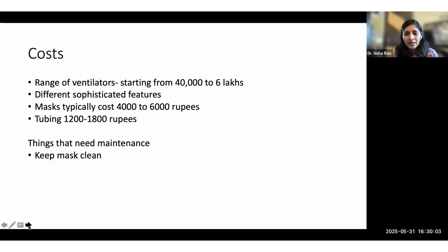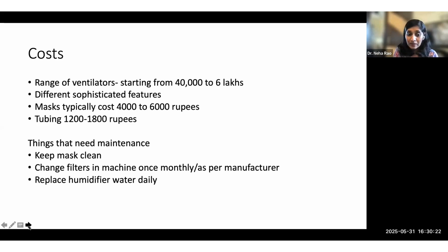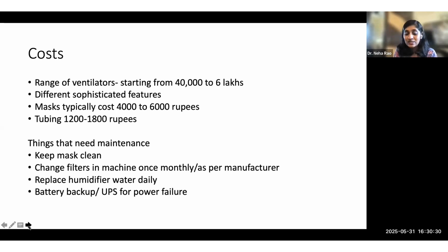There are some things that need maintenance. For example, we need to keep the mask clean. We need to change the filters in the NIV machine as per the manufacturer's recommendations, usually once a month. We have to keep the water in the humidifier clean. We usually use either distilled water or boiled and cooled water, but there are specific instructions from manufacturers, and we have to keep the water in the chamber clean. We also need to have a UPS or battery backup in case of power failures, because these are machines at the end of the day, and if they give up on us at night, then it's quite difficult to manage.